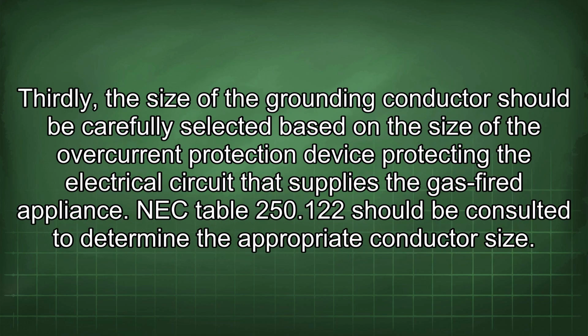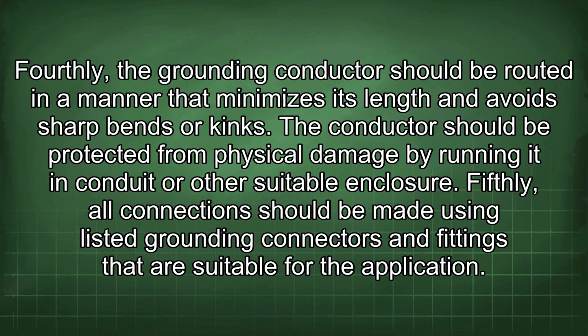Thirdly, the size of the grounding conductor should be carefully selected based on the size of the overcurrent protection device protecting the electrical circuit that supplies the gas-fired appliance. NEC Table 250.122 should be consulted to determine the appropriate conductor size. Fourthly, the grounding conductor should be routed in a manner that minimizes its length and avoids sharp bends or kinks. The conductor should be protected from physical damage by running it in conduit or other suitable enclosure.